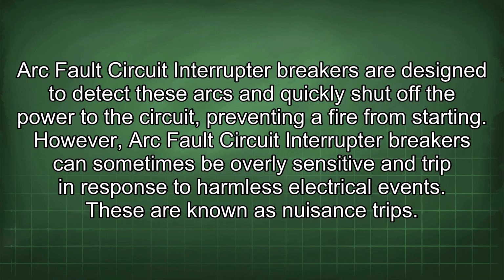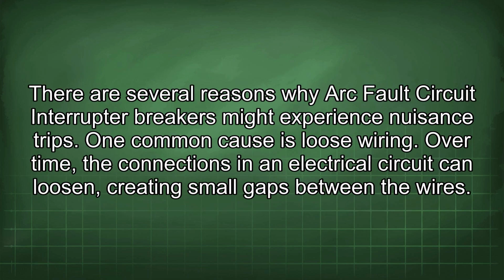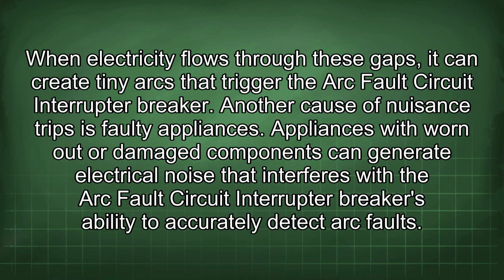However, arc fault circuit interrupter breakers can sometimes be overly sensitive and trip in response to harmless electrical events. These are known as nuisance trips. There are several reasons why arc fault circuit interrupter breakers might experience nuisance trips. One common cause is loose wiring. Over time, the connections in an electrical circuit can loosen, creating small gaps between the wires. When electricity flows through these gaps, it can create tiny arcs that trigger the arc fault circuit interrupter breaker.